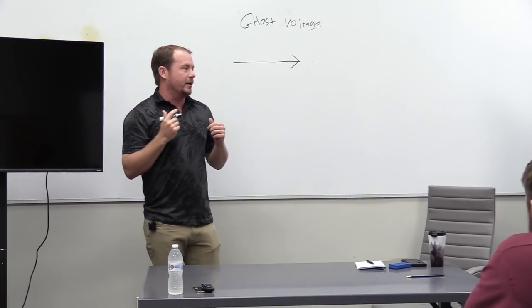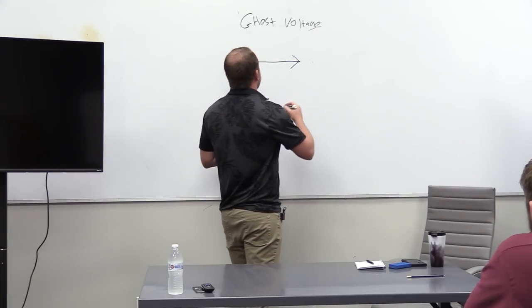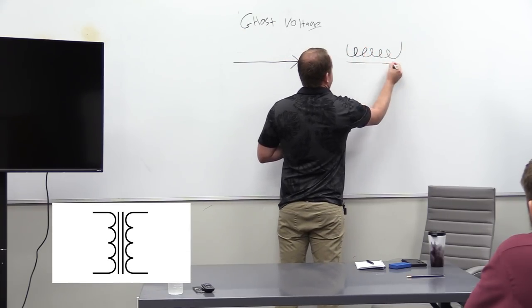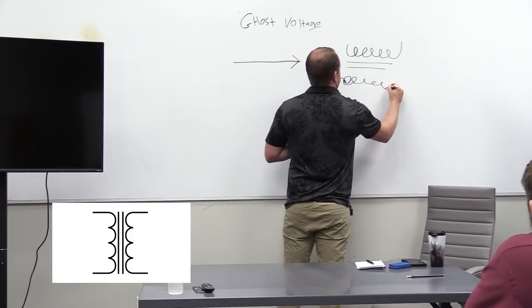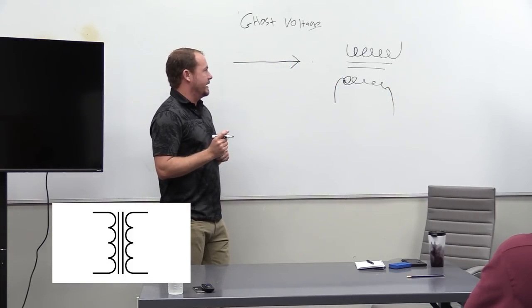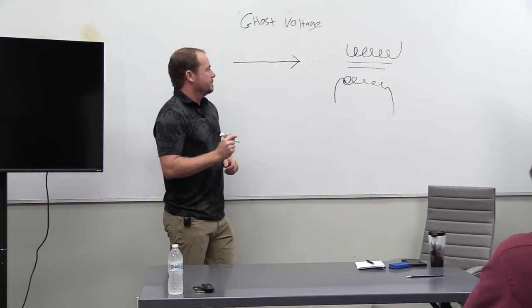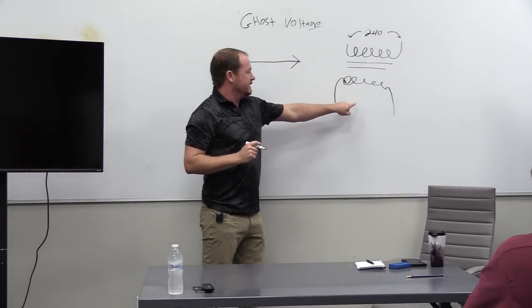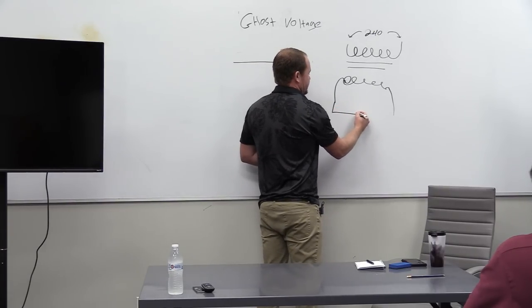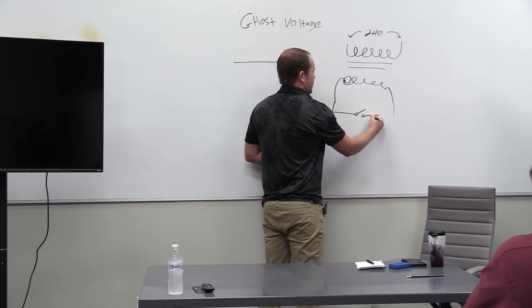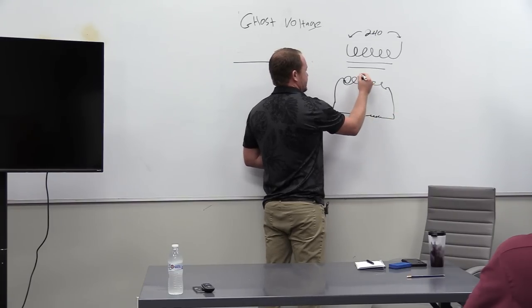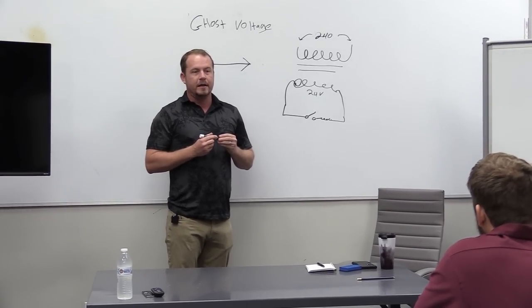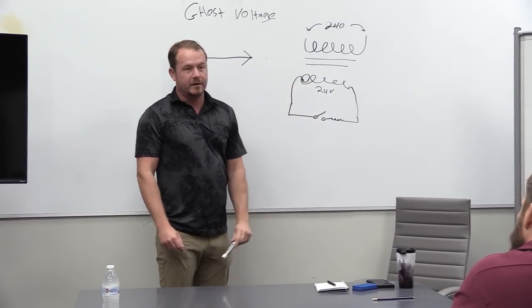Let's look at it from a more basic standpoint. There's a couple of different things that can go on here. If you've got a wire and it is being energized. So let's imagine, you've maybe never thought about this before, but if you have a transformer, so a transformer symbol, I always like to kind of draw the symbols for things. When you energize the primary on a transformer, we're going to say we energize it with 240 volts, but this circuit is open. We have a switch here and it's open. And then we have a load, maybe it's a contactor coil, whatever. And this is 24 volts here. When we energize the primary on this transformer, does the transformer draw any current when the secondary is open?